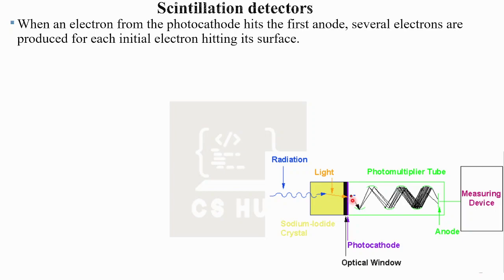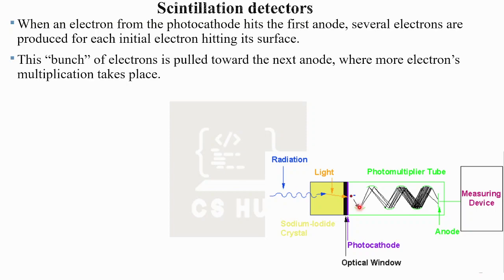The first electron generated by the photocathode hits the first anode. When an electron from the photocathode hits the first anode, several electrons are produced for each initial electron hitting its surface. So one electron strikes the anode and several electrons are generated. This bunch of electrons is then pulled towards the next anode, where more electron multiplication takes place.